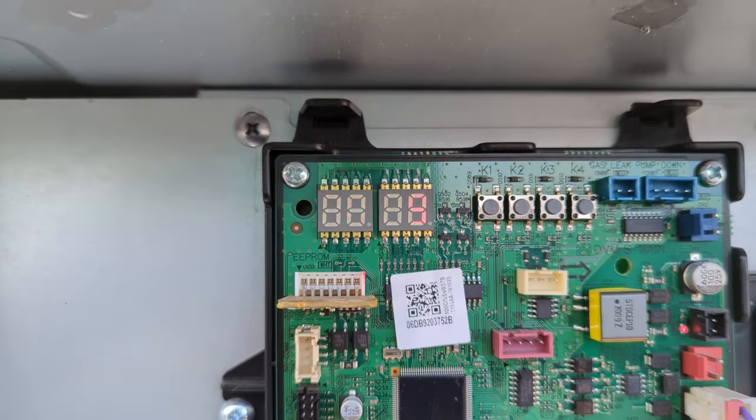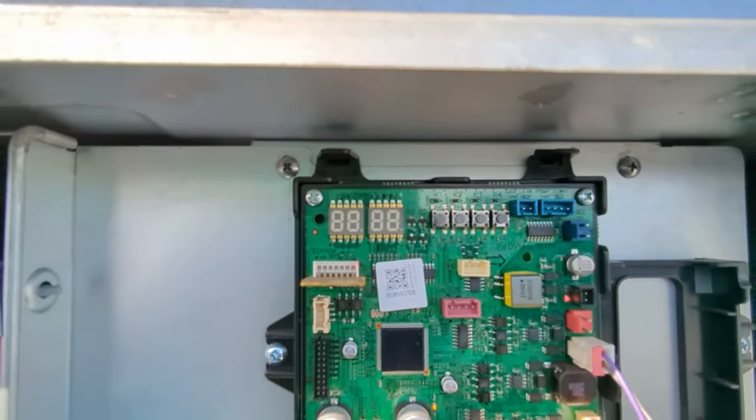So tricky too, because we did the thing, and then it seemed like the system was cycling, it seemed like it was trying to map all of the indoor units. And it would just keep counting up and then restart and keep counting up and then restart. And because we're not super familiar with Samsung VRFs, we actually called technical support back and we were like, this thing is just cycling through its mapping. And they're like, no, that's normal operation. So if you work on Samsung VRFs, normal operation cycles through that little counter.